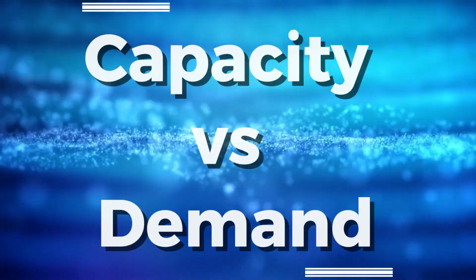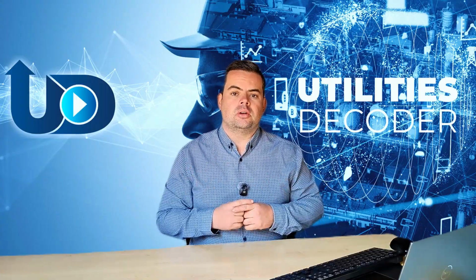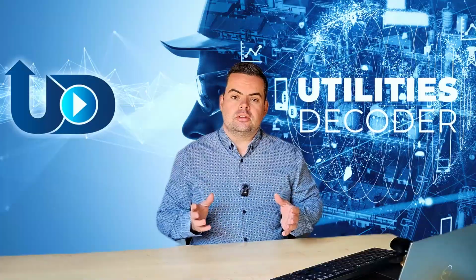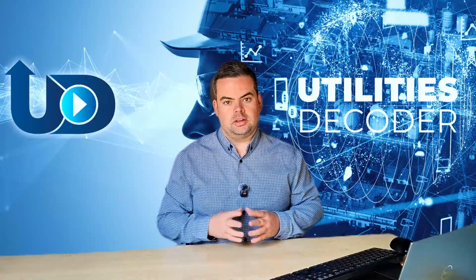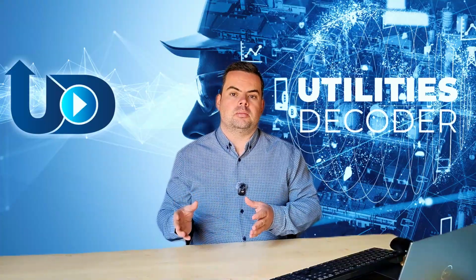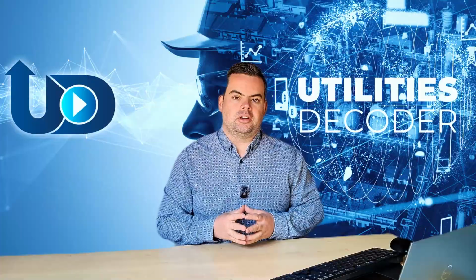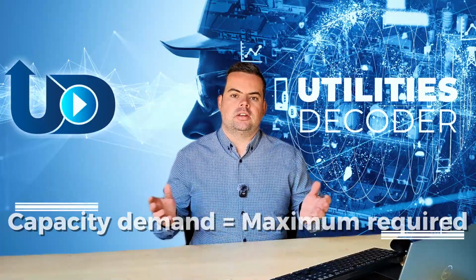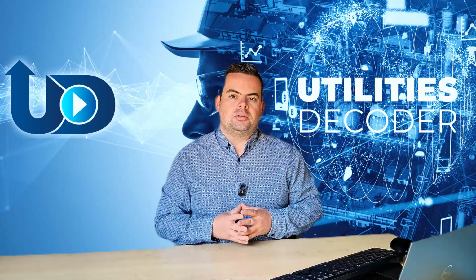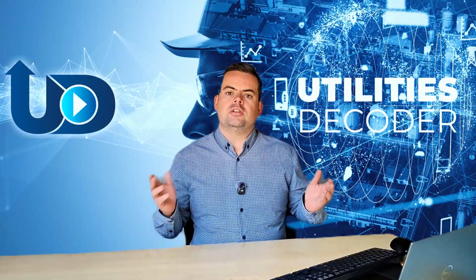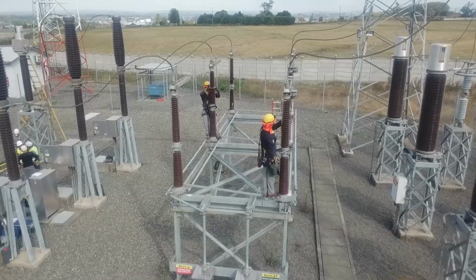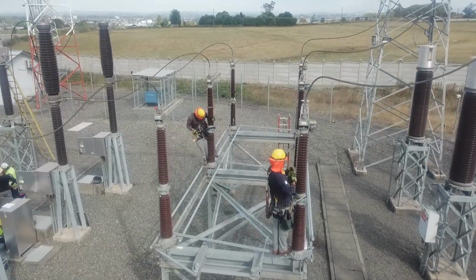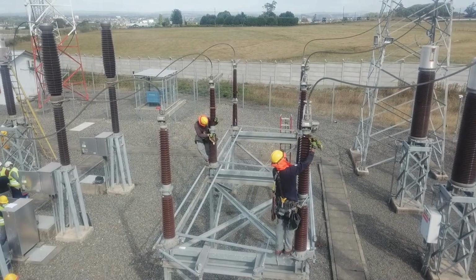Capacity versus demand charges. Now this is where it gets a bit trickier, but don't worry, we're going to make it simpler for you. There are two terms that sound similar but mean two different things. We have capacity or notified demand and demand charge. Capacity demand is the maximum amount of power you tell the authorities that you need. Let's say, for example, you're a business and you sign a contract for 350 kVA. If in the month you only use 280 kVA, you unfortunately will still be liable for the full cost of the 350 kVA. And that is because the utility builds infrastructure such as cables and transformers to be able to withstand those maximum loads. Great.